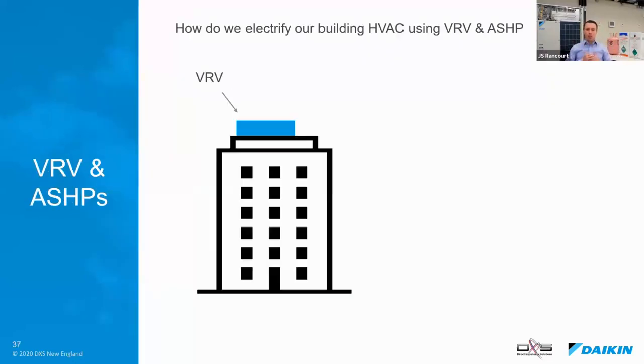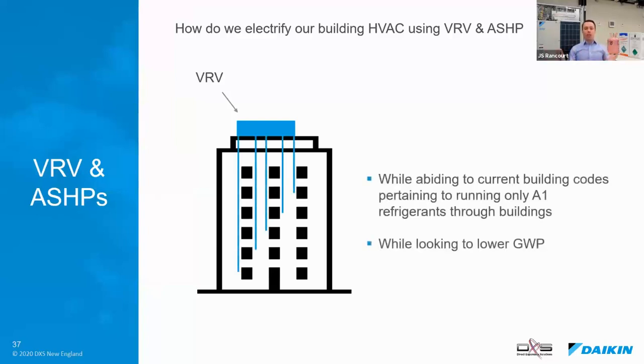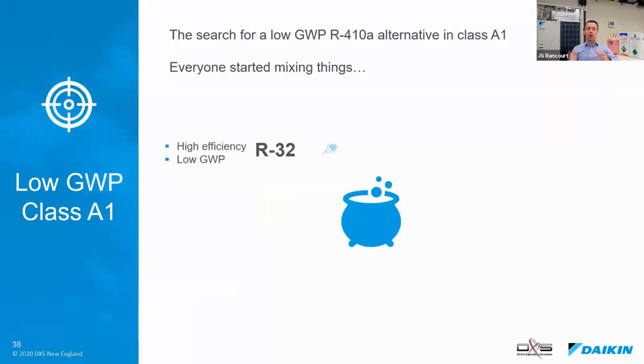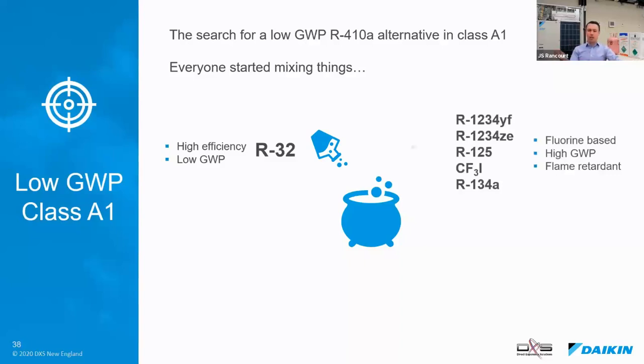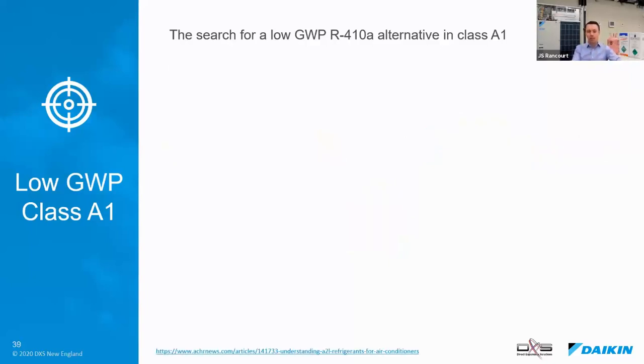Back to electrifying buildings with VRV and air source heat pumps. How do we abide by the current building codes, which only allow us to run A1 refrigerants through buildings, while lowering GWP? Well, this started the search for low GWP R410A alternatives that are still A1 refrigerants. Everybody's been going through their chemistry labs and mixing things. It all starts with our beloved high efficiency R32, and they started mixing other refrigerants and chemicals in there. You're going to see some funky letters up there, 1234yf, 1234ze. Those are hydrofluoroolefins. I won't get into those today. But everybody's mixing in some sort of flame retardant, some way to try and get R32 into the A1 category.